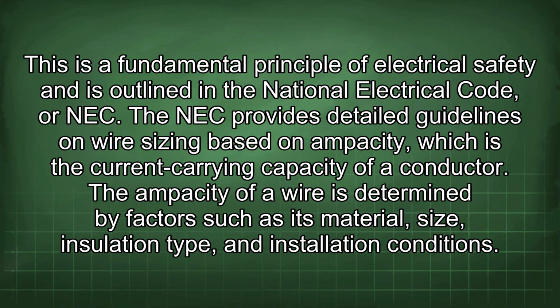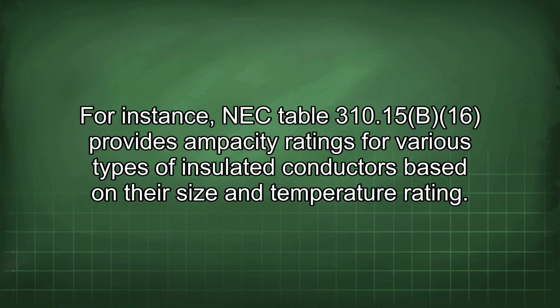This is a fundamental principle of electrical safety and is outlined in the National Electrical Code, or NEC. The NEC provides detailed guidelines on wire sizing based on ampacity, which is the current carrying capacity of a conductor. The ampacity of a wire is determined by factors such as its material, size, insulation type, and installation conditions. For instance, NEC Table 310.15(B)(16) provides ampacity ratings for various types of insulated conductors based on their size and temperature rating.